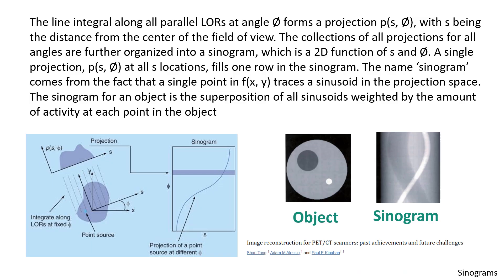All coincidences have to be organized to be used for image reconstruction. PET data are organized in sinograms. We consider the line integral along all parallel lines of response at a specific angle, forming a projection that depends on two parameters: the considered angle and the parameter S, which is the distance of each point in the projection from the center of the field of view. The projections at all angles around the object are organized into a sinogram, which is a 2D function of S and angle. Each projection is a line in the sinogram. The name sinogram comes from the fact that a single point traces a sinusoid in the projection space, so the global sinogram is the overlap of all sinusoids, each weighted by the amount of activity in each point.